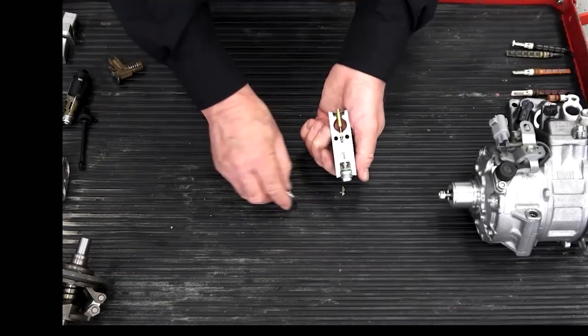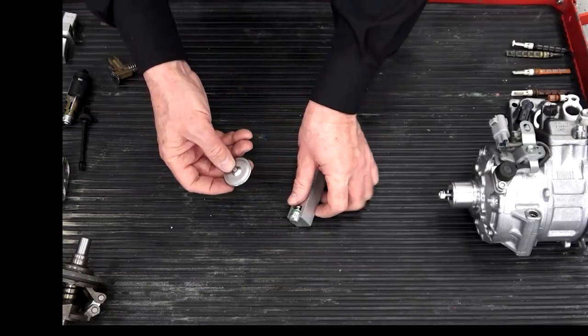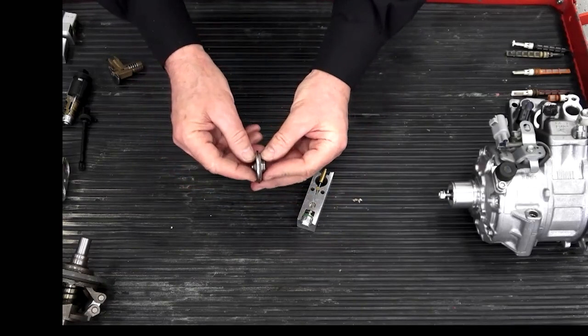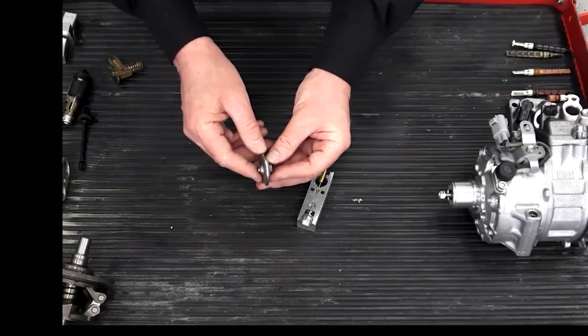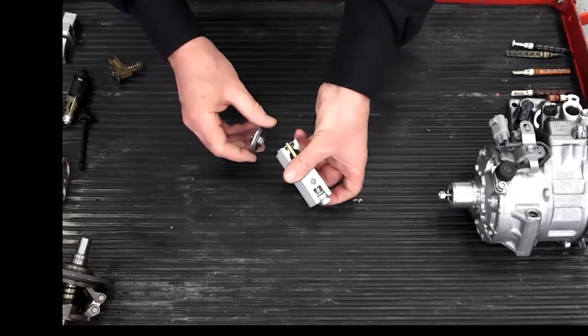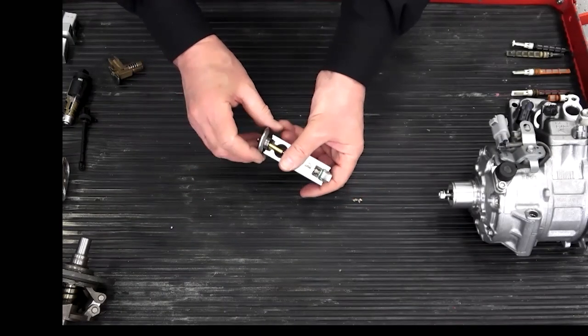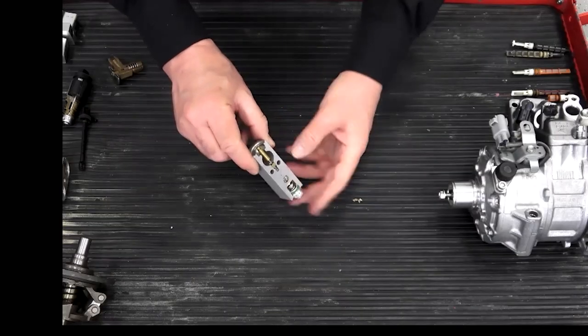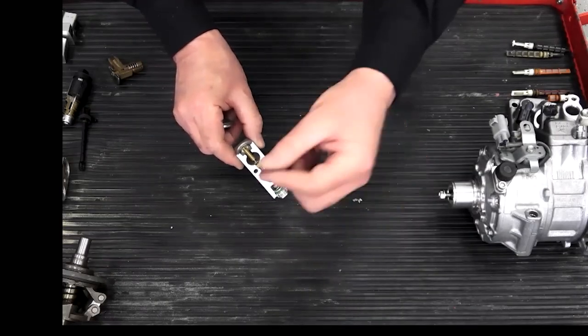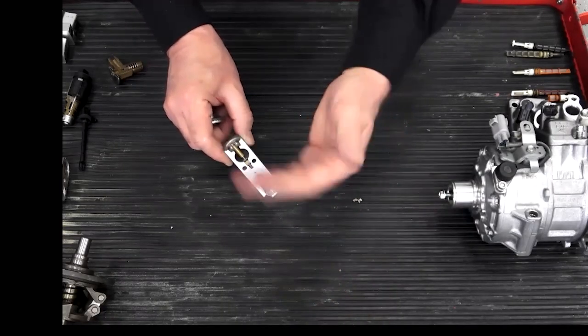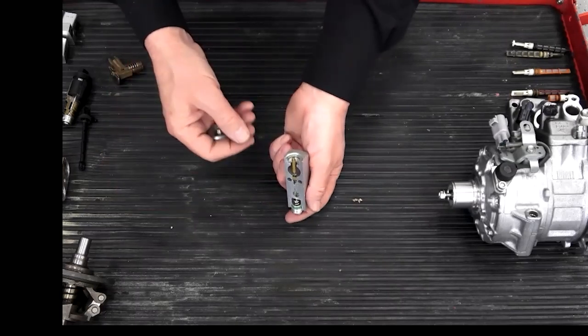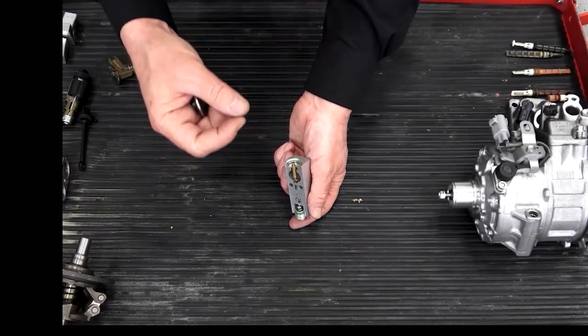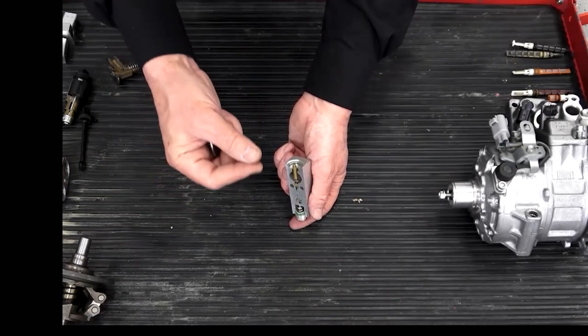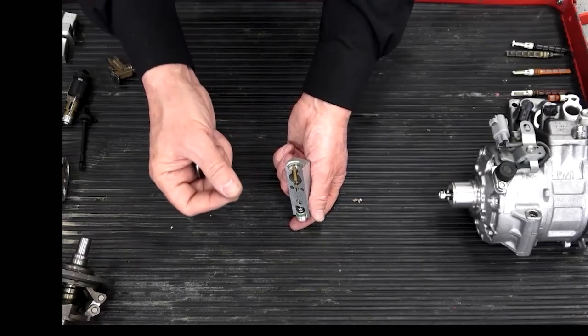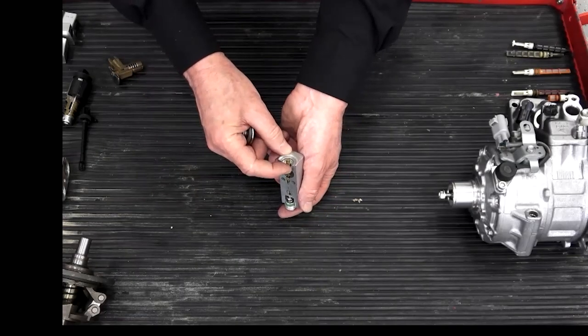that ball valve. Well, when this power element is manufactured, it has a small amount of refrigerant gas trapped above the diaphragm. So if liquid refrigerant comes into the evaporator, it boils, changes state, and starts coming out the top. In a TXV system, I'm going to allow a small amount of superheating. In other words, I'm going to allow all the liquid to change state from a liquid to a gas so that it's pure gas coming out the top.